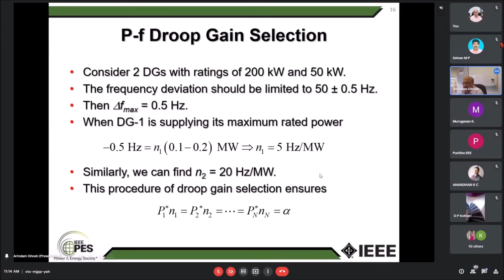So that's important. And the other thing that you can do is the same thing in the same way, and you can find N2, which is this one, 50 kilowatt, will be 20 hertz per megawatt. So for each megawatt change, the frequency will change by 20 hertz. In fact, if you follow the same procedure, the Droop gain you will be selecting is P1 times N1 equal to P2 times N2 up to Pn times Nn equal to alpha. There will be a constant. In fact, if you look at this, this is 5 times 0.2 is equal to 1 hertz, and 20 times 0.05 is also 1 hertz. Okay, so something like that. So this is the Droop gain selection.